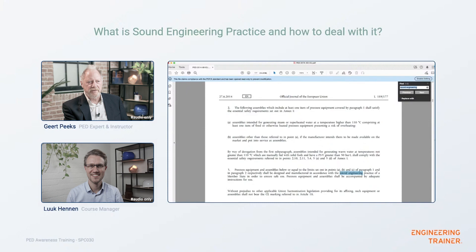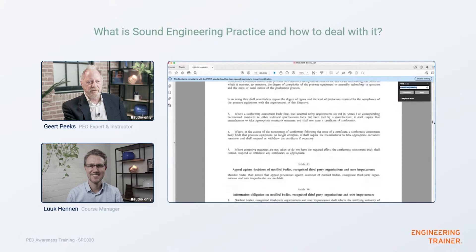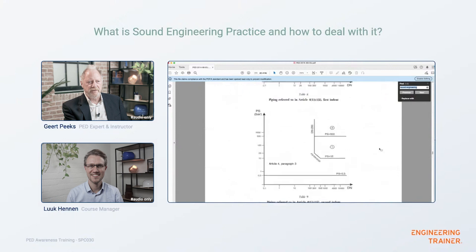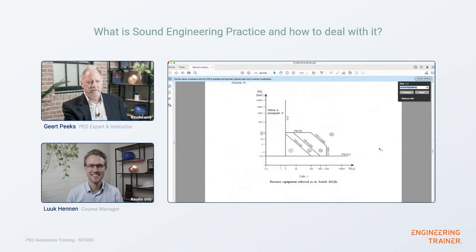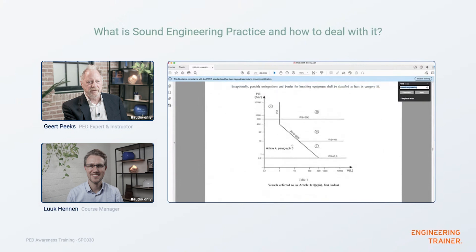When you do that classification — also based on the kind of fluid inside your pressure vessel or piping — you end up with a category from the tables in the Pressure Equipment Directive: category one, two, three, or four. For piping, the highest category is category three. But there is also what we sometimes call pressure equipment in category zero — not an official term in the directive — where even high pressures with small volumes or small pipe diameters can be considered Article 4 paragraph three equipment, defined as sound engineering practice.